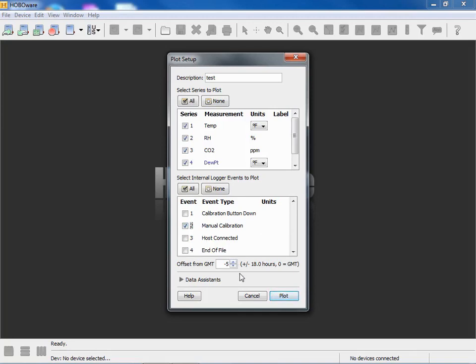And again, we have the ability to put in an offset from GMT, or what is called UTC time, just like any other logger from Onset. The logger gets its date and time from the device that it's being launched from, be it a computer, a smartphone running the HOBO mobile app, or a tablet, or a shuttle device. So all we're doing when we're selecting an offset from GMT is we're selecting to offset the time reference for the plot for display on the screen. It doesn't affect the original data file.